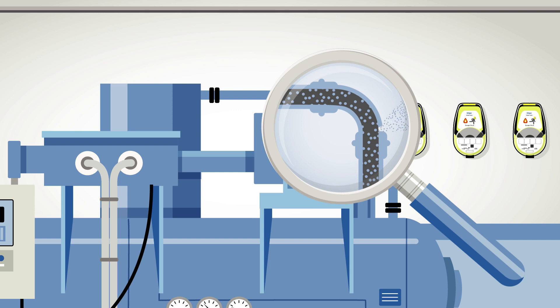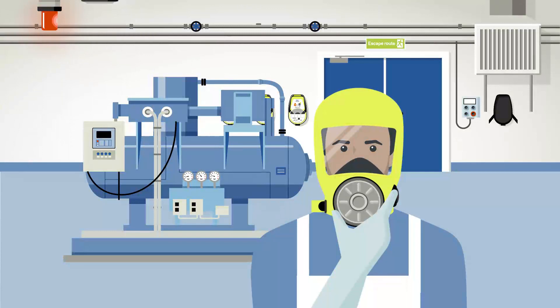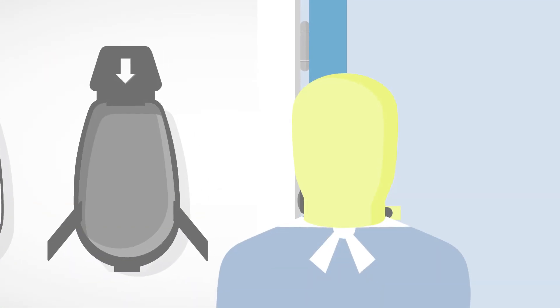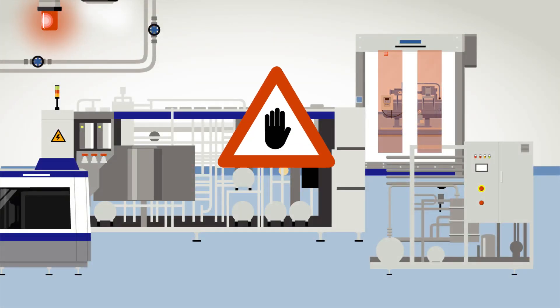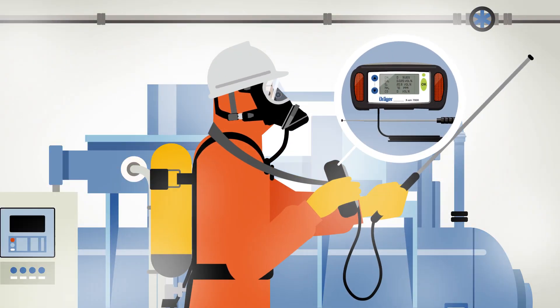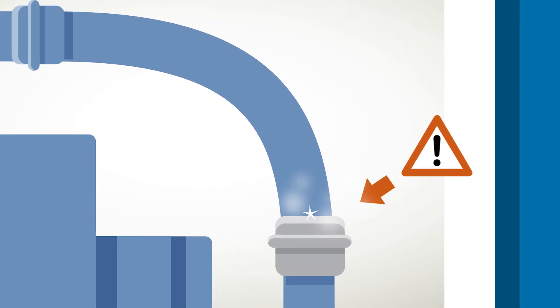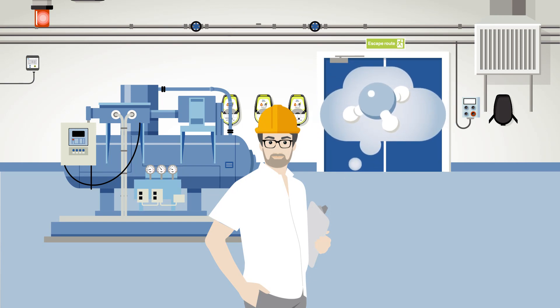A mistake can lead to a momentous leakage, and consequently the gradual escape of ammonia. The dangerous ammonia concentration in the air causes an immediate gas alarm. The measures developed by the safety management then take effect, and employees must leave the plant immediately. The consequence of such accidents is obvious — production is down, and produced goods can be contaminated, regardless of whether it was a real or false alarm. That's why leaks in particular must be reliably detected. For locating leaks, additional portable gas detectors are required for the emergency personnel. Only when the leak is repaired can production be restarted. The safety engineer is responsible for the measures which ensure a safe usage of ammonia in the plant.